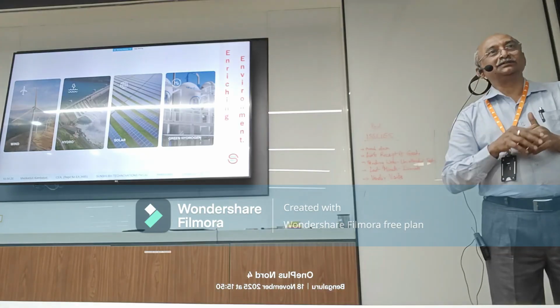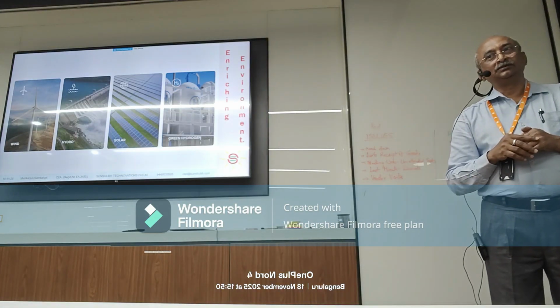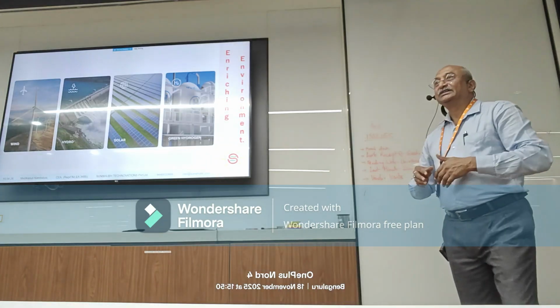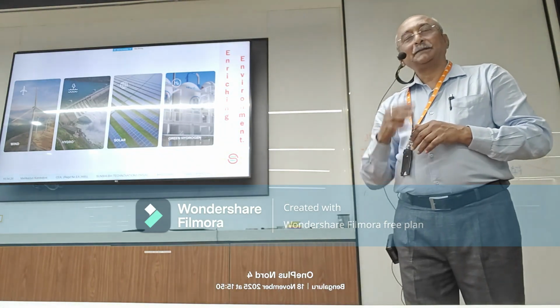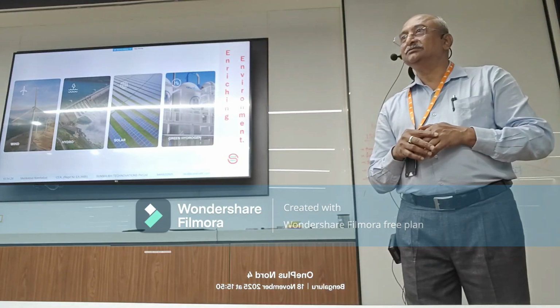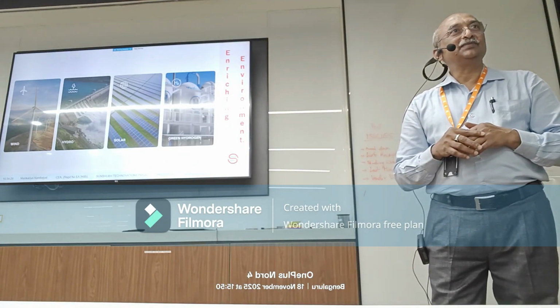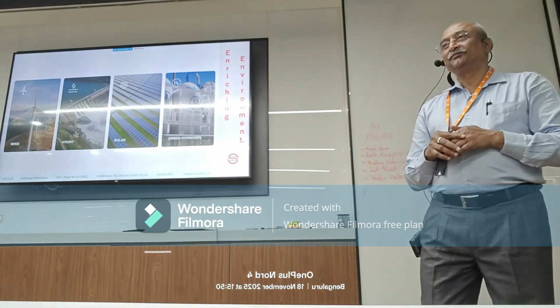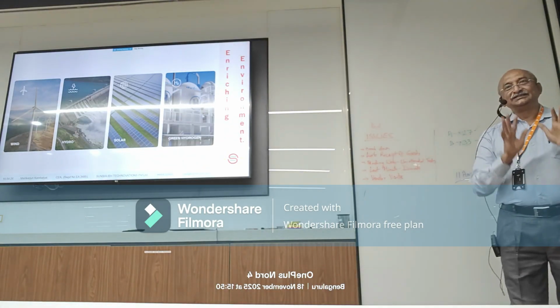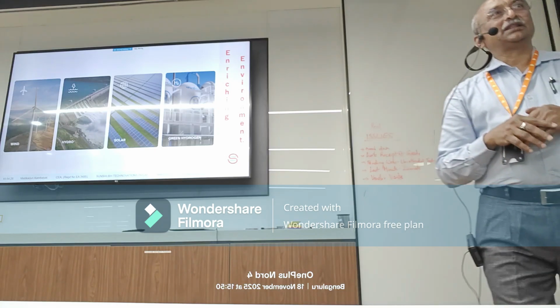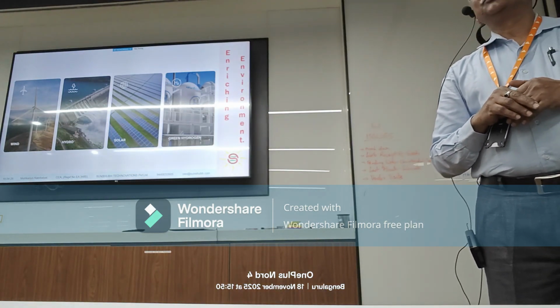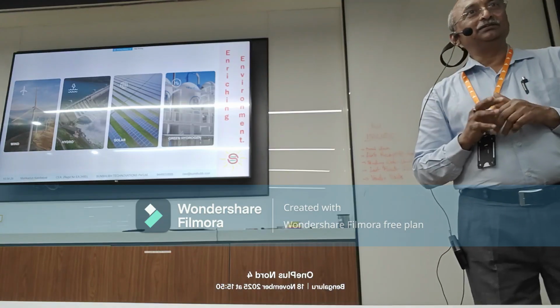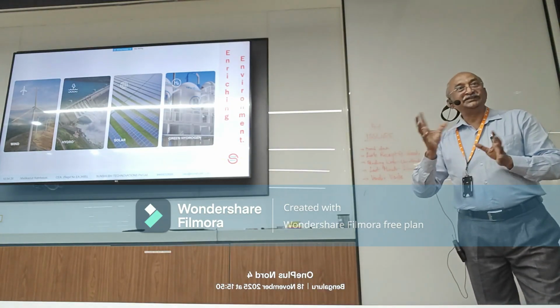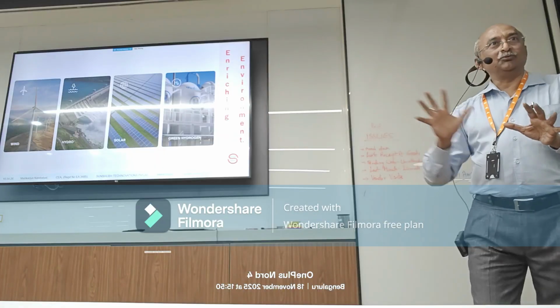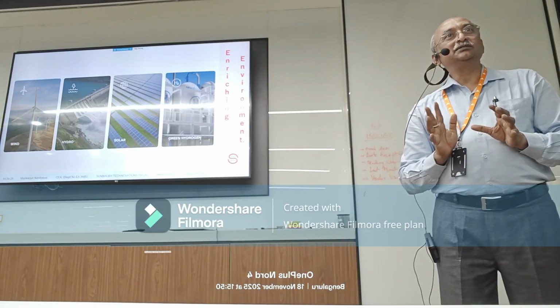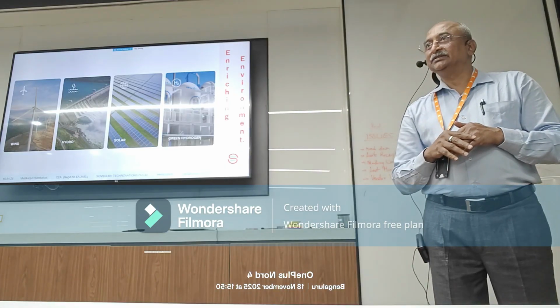Okay, how many units? Around 2,20,000. So divide 2,20,000 by 30, that gives around 7,000 units. Divide 7,000 by 24, that's around 305. Multiply this by 1.5 to account for daytime and nighttime load, so 305 times 1.5 is about 458, say around 600 kilowatt.